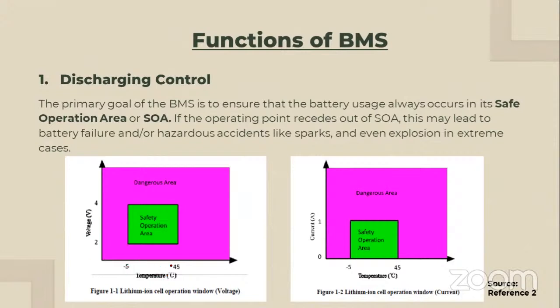In this case, we've taken the range as -5 to 45 degrees, but in the automotive domain, on vehicles I've worked on, it generally ranges from -30 or -40 degrees up to 120 degrees. So if the battery pack senses its temperature—due to ambient conditions or cooling system failure—crossing 120 degrees, or sometimes 100 degrees, the BMS has to either disconnect the battery pack from the system or command other ECUs to operate in derating mode, so the pack isn't overheated further and overall stress is reduced.